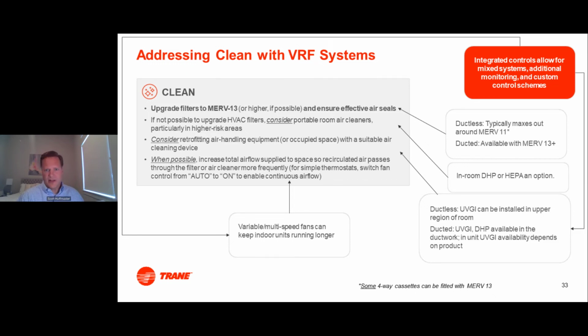One of the challenges with the MERV 13 filter approach is if you have a system that reduces the amount of airflow, you lose some of the effectiveness because your clean air delivery rate is going to go down. So we want to look at where possible using controls to increase airflow and keep those filters running. So what does all this mean when we talk about VRF? Again, integrated controls is a big piece of this.